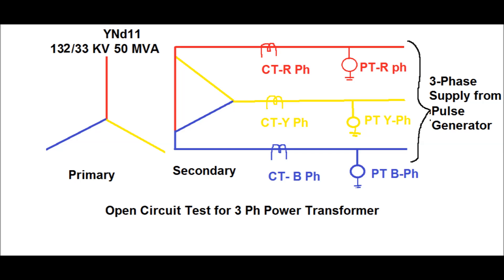The LV side, that is the delta side, is 33 kV, therefore from the pulse generator a 33 kV voltage supply has been given. This test is mainly done at the factory to measure and record the no-load losses. The no-load current and no-load losses are measured by the secondary input of PT and secondary input of CT connected in each phase, as shown in this diagram.